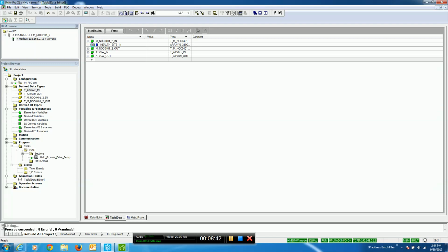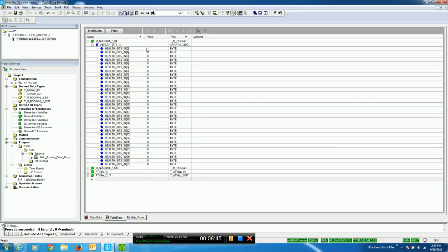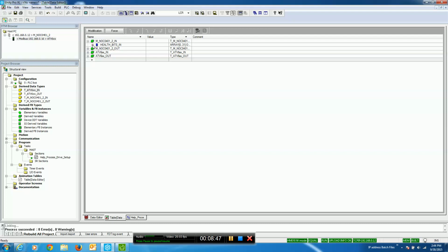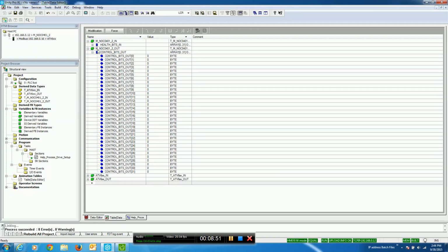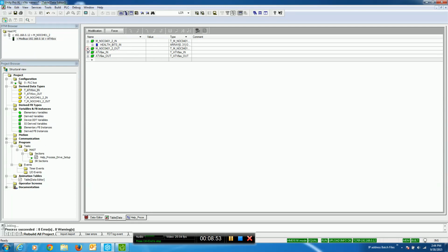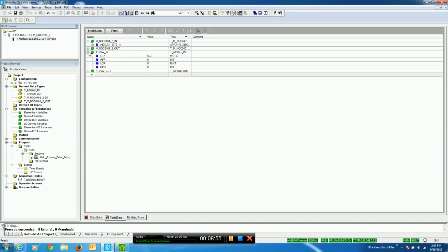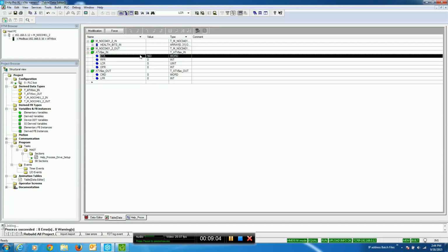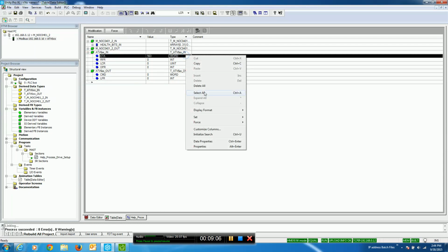So now when I click here and look at the health bits, I can see that I'm connected properly for the health bits in on the NOC. On the control bits, I'm not controlling anything right now, so that's fine. I'm going to go to the ATV61, and I can see that it actually added these variables as a structure exactly the way I looked at it.